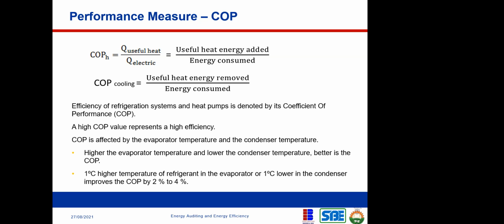It goes ahead to tell you that a 1 degree centigrade higher temperature of your refrigerant in the evaporator, or 1 degree centigrade lower in the condenser, improves your COP by 2 to 4%. So the temperature of your cooling system is very, very important, whether the evaporator or the condenser, to their efficiency status. We need to pay attention to this, and we need to understand how they affect their efficiency and performance.